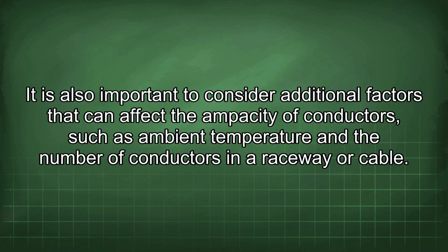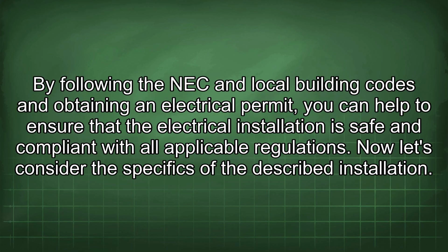It is also important to consider additional factors that can affect the ampacity of conductors, such as ambient temperature and the number of conductors in a raceway or cable. By following the NEC and local building codes and obtaining an electrical permit, you can help to ensure that the electrical installation is safe and compliant with all applicable regulations.